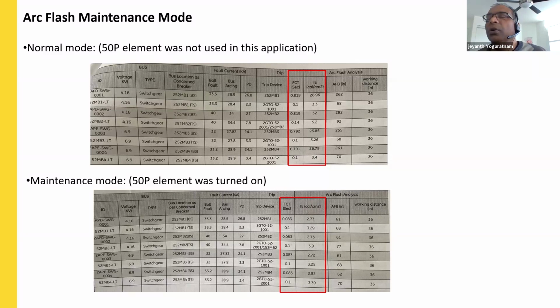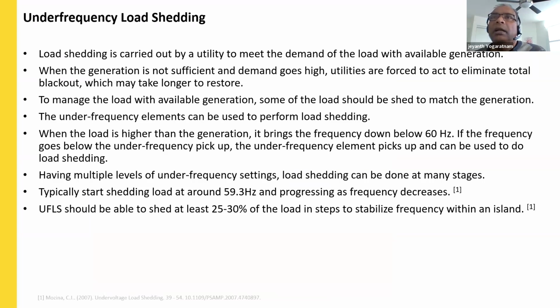They expected that to happen. So during the maintenance mode, we wanted to switch a group and provide the arc flash mitigation. The other functionality I want to talk about is under frequency load shedding. Technically, it comes to manage the load with the available generation. In a situation when generation is not adequate to support the required load, the utilities or even any applications are required to cut down some of the load. That is called load shedding. The under frequency element can be used to perform this load shedding functionality.